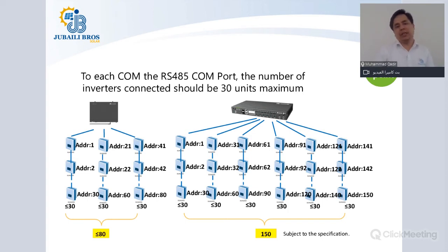But with the smart logger 3000A, across all COM ports, you must keep the number of solar inverters less than 80, which accommodates most of your commercial and industrial size projects, because 80 inverters is a high number. Normally the smart logger 3000B, which has 6 COM ports, is used for utility scale projects, and this smart logger can accommodate up to 150 solar inverters. In this scenario again, to each COM port you can connect up to a maximum of 30 solar inverters using RS485 communication.